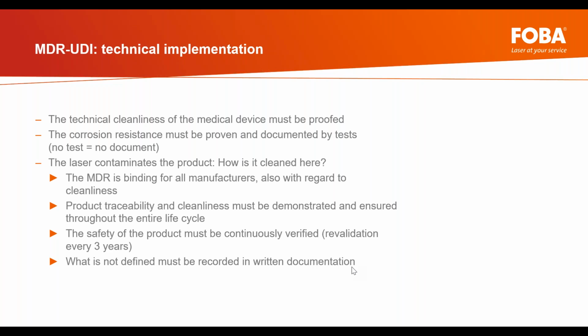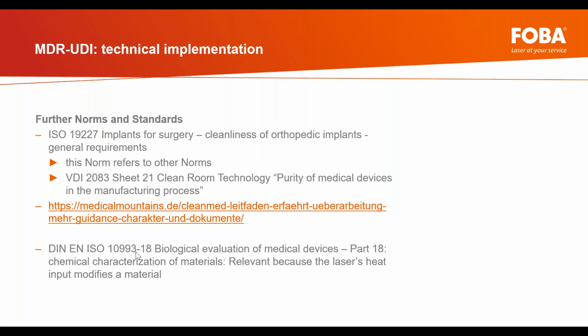And from the autoclaving cycles, I can say it took very long, I think more than 6 months, because after all autoclaving, it has to be dried out. We challenged the surface with a pH value of 14, which is really tough, like a stress test for the material. And last but not least, the test was redone in January with 40 cycles, receiving the same results. So we can provide you a paper for this when you start with us. This doesn't replace your own test, but it helps you, so that the manufacturer also tested it and knows there is a really safe and secure validation process.